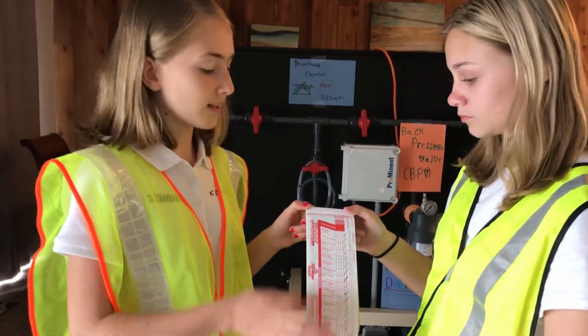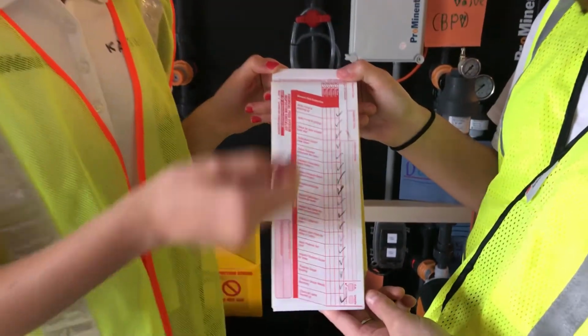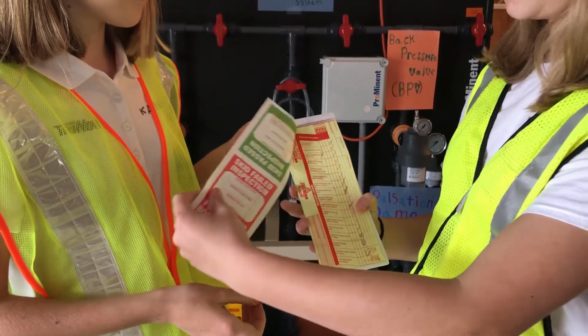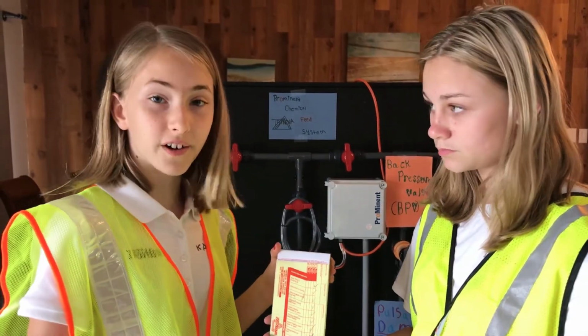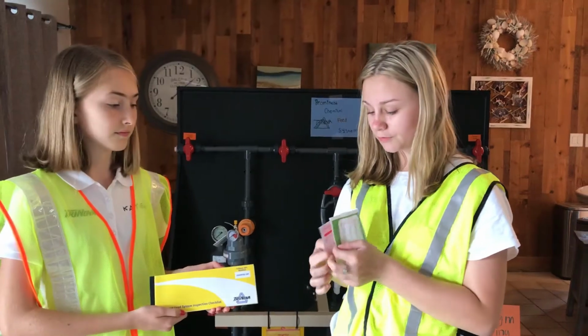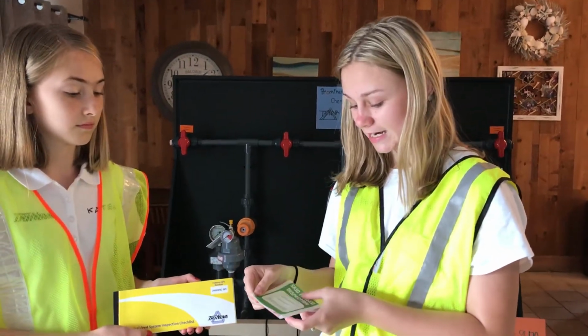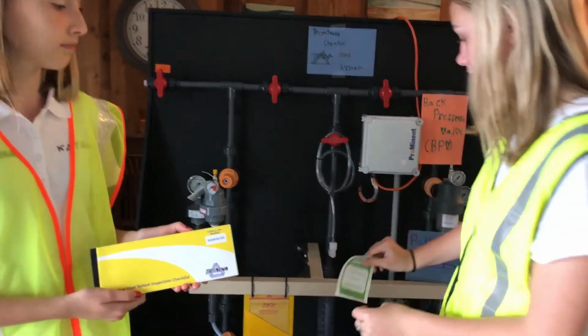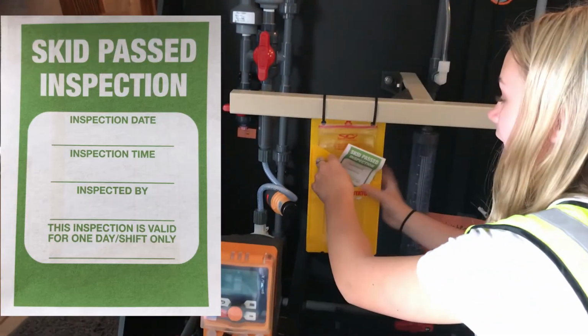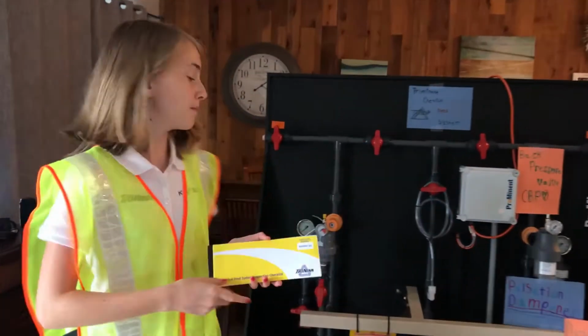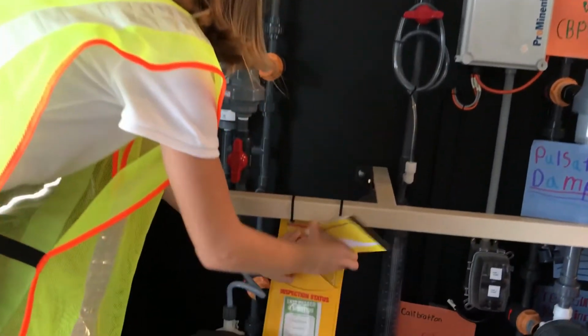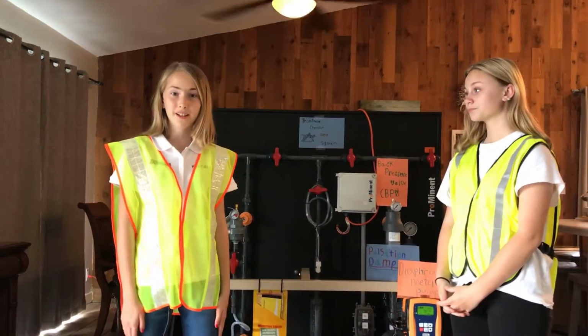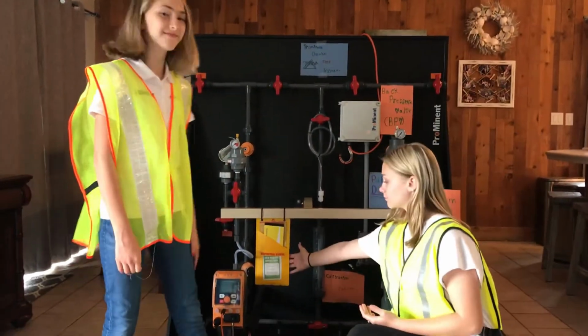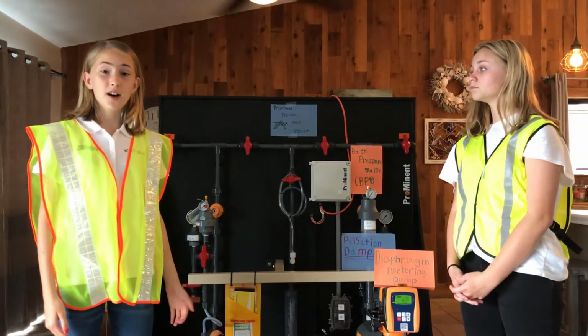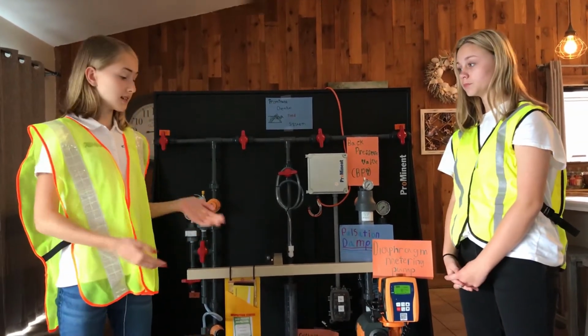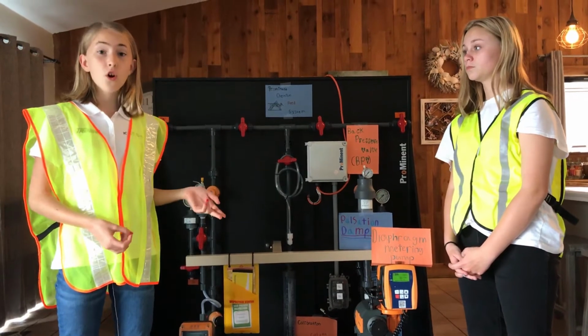So we've completed our booklet and we've made sure everything is working properly. So we're going to tear this off. This is a second copy, so you'll always have records of the inspection. Now you're going to fold it in half, and then you're going to sign and date it, and then you're going to stick it in the slip here, whether it passed or failed. You can keep your booklet with the skid. So we've completed our inspection and our skid passed. This is a great tool, so it allows anyone walking through the plant to know if this skid is working, in good condition, or needs service.